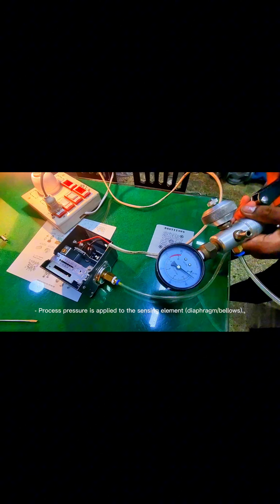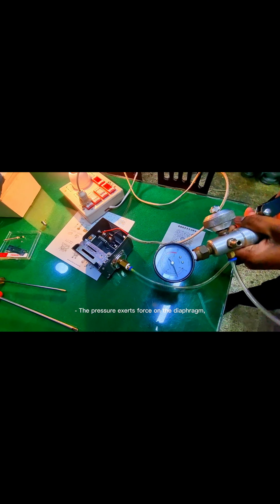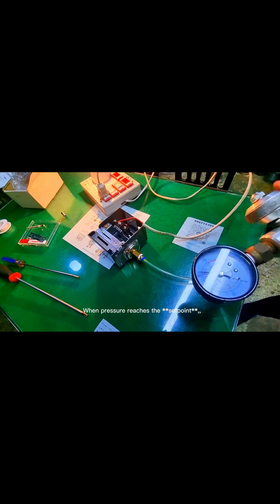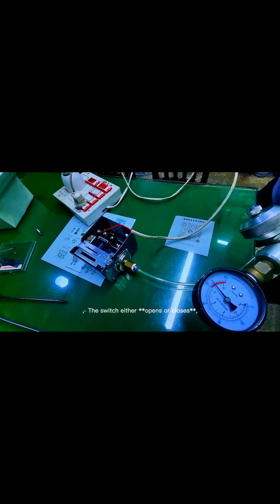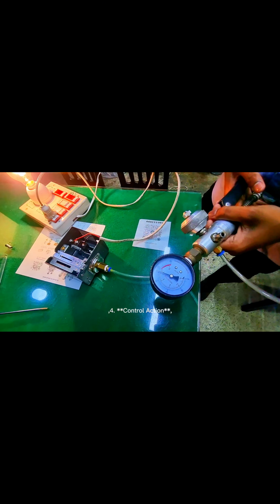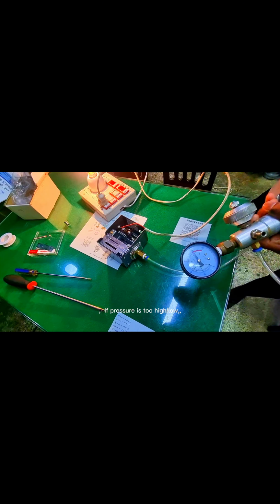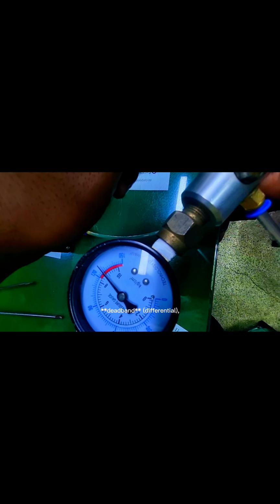Pressure application. Process pressure is applied to the sensing element, diaphragm, bellows. Force comparison. The pressure exerts force on the diaphragm, compressing a spring. Switch activation. When pressure reaches the set point, the diaphragm moves enough to trip the microswitch. The switch either opens or closes an electrical circuit, NO/NC contacts. Control action. If pressure is too high or low, the switch signals a pump or valve to turn on or off. Reset, hysteresis. The controller may have a deadband or differential to prevent rapid cycling.